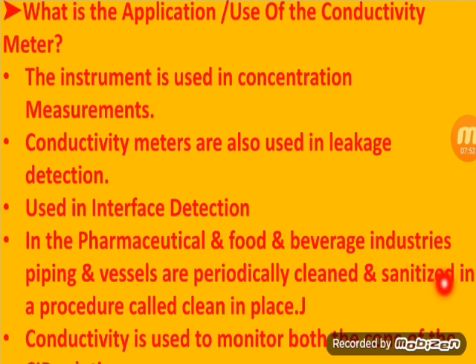In the pharmaceutical and food and beverage industries, piping and vessels are periodically cleaned and sanitized in a procedure called Clean-In-Place (CIP). The conductivity meter is an important instrument here. The CIP solution pipelines are monitored, and the concentration and water treatment plant operations are checked regularly. We examine samples to see how much concentration is present.